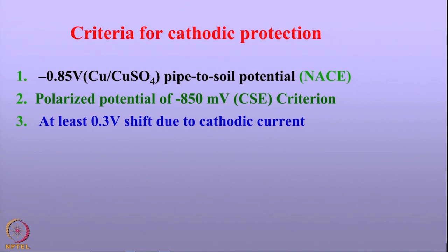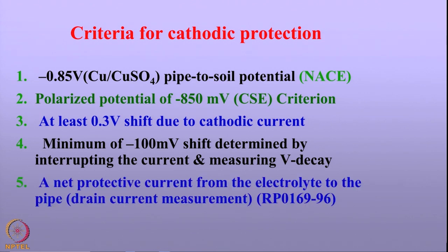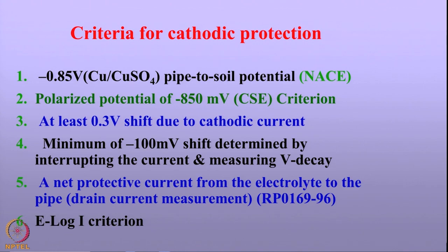Another criterion is a 0.3 volt shift from the corrosion potential or the natural potential of the metal towards the negative direction. The fourth criterion involves shifting the potential by 100 millivolts, determined by interrupting the cathodic protection current and measuring the voltage decay. There is also a criterion based on a net protective current from the electrolyte to the pipe, called a drain current measurement. The last criterion is based on a potential versus log i curve determined for a given structure. We shall look in detail at the merits and demerits of these criteria.